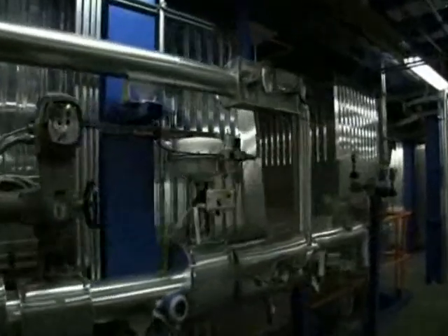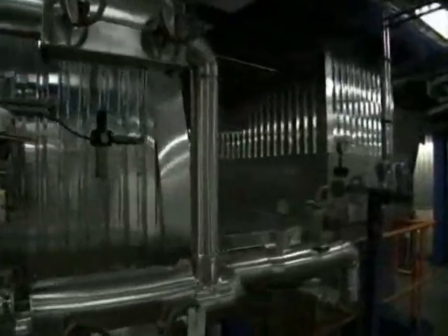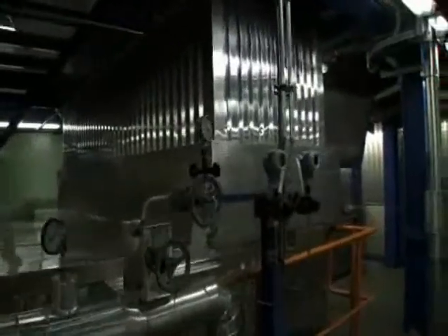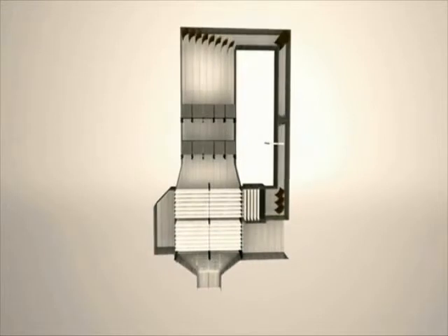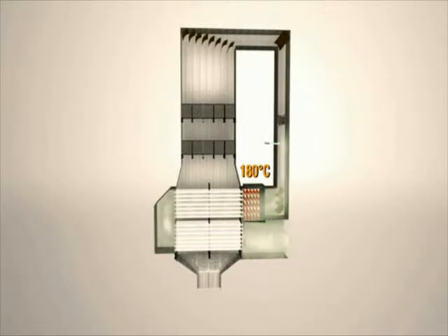Round 4. The Denox unit. Now fast reaction is necessary. Unwanted nitrogen oxides are removed here. Before entering the Denox complex, the flue gas is sent once again through a heat exchanger and heated to a temperature of 180 degrees centigrade. Now ammonia water is added to the flue gas by means of jets. After mixing well, it moves on to the catalyzers.